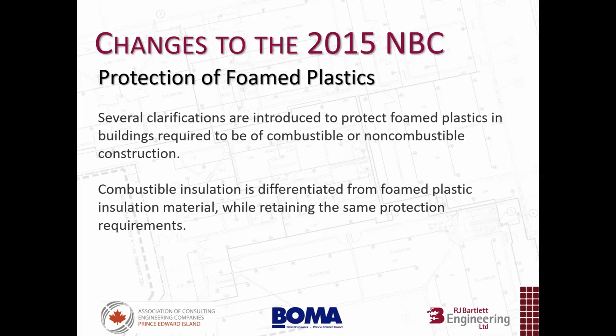Some clarifications on foam plastics are now introduced to the 2015 code, in both the requirements regarding combustible and non-combustible construction. The big one is that combustible insulation is differentiated from foam plastic insulation material. In summary, the protection requirements are very similar. My understanding, one of the reasons for this, is that foam plastics can behave differently than other combustible insulation. They will melt and even drip and spread differently because of that material property. So that's, I believe, a driving force for this differentiation.